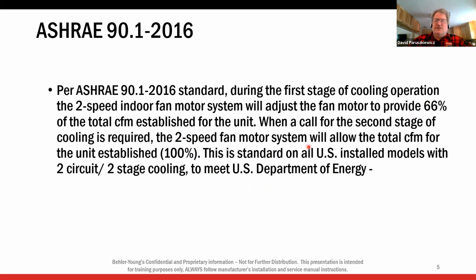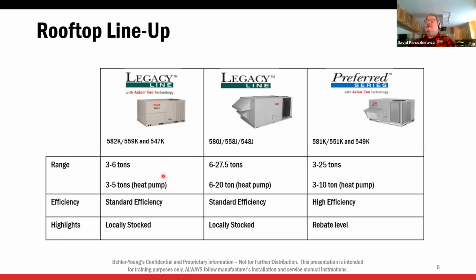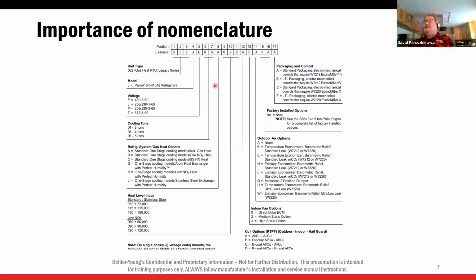So the first part we're going to break the unit down into sections. First we're going to look at the blowers on the smaller units, and then get into the larger units. So the 3 to 6 ton, which is the 582K, we're going to break down into one section, and then we're going to jump up to the 580J, which is the 7.5 to 27.5 ton units. Those are primarily the units that we're going to have in the field, the 580J and the 582K. Now the 582, there's a 3 and 4 ton, which still is a single speed blower. So we don't go to the 2-speed until we get to the 5 ton. And then the entire 580J family does have a 2-speed blower. So you're not going to get away with it.